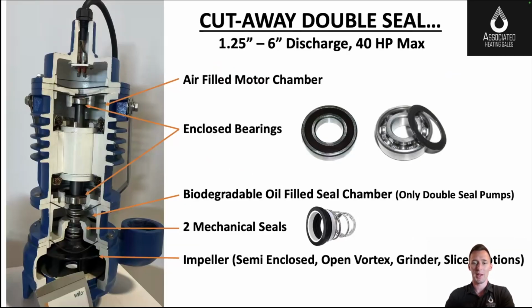Here's a Wilo cutaway of a double seal pump. Starting from the bottom, you have the impeller, the case where the fluid enters the pump. Then you have the seal chamber next. This is a double seal pump because you have two mechanical seals, one on either side of the seal chamber. You have biodegradable oil here. This makes this larger pump longer lasting. The seal chamber will push away water or debris that's getting into the pump as this seal fails. We'll talk about sensors later that are placed within the pump that can tell maintenance personnel that this pump is starting to leak or the seals are starting to break down.